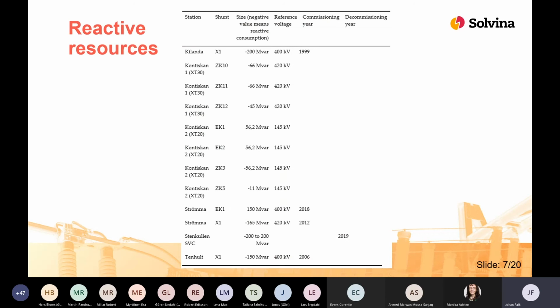In this region we have a number of reactive resources, which could be found in the area during the investigated time period for this study. And this time period is from 2015 to 2019. The ones named Kontiskan in this list are located in Lindome to offset the non-linear reactive power consumption of the HVDC Classic link we can find there. And therefore we don't focus much on these resources in the report.